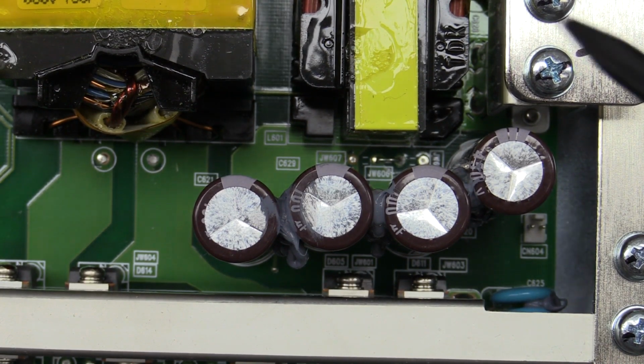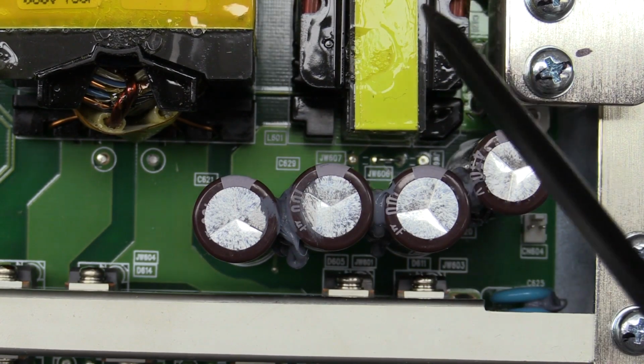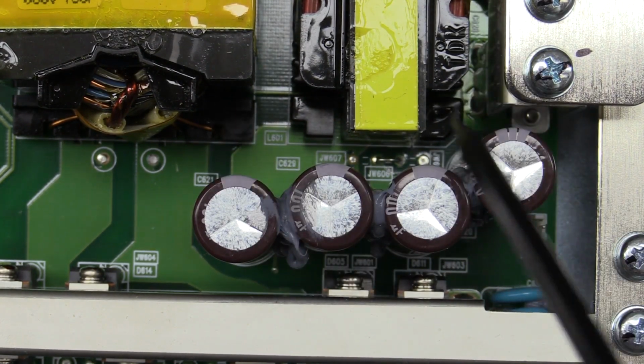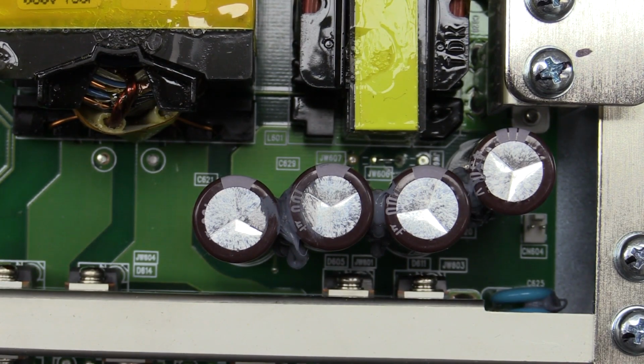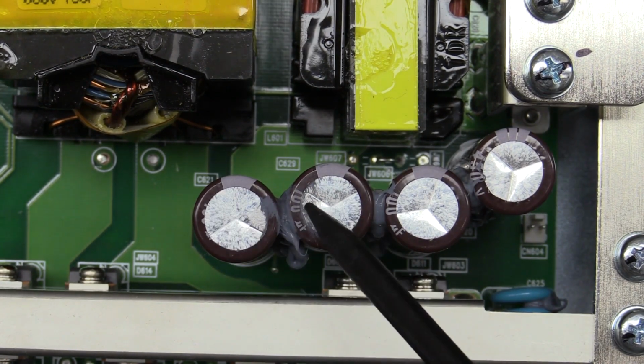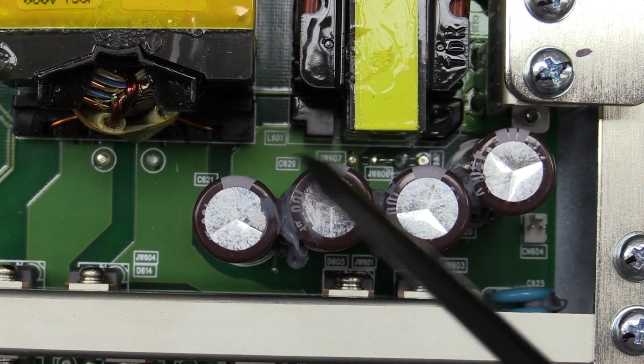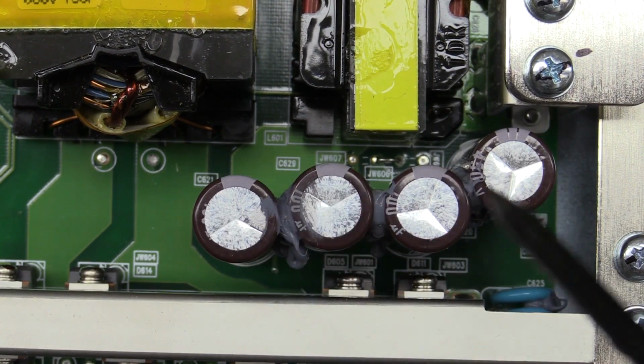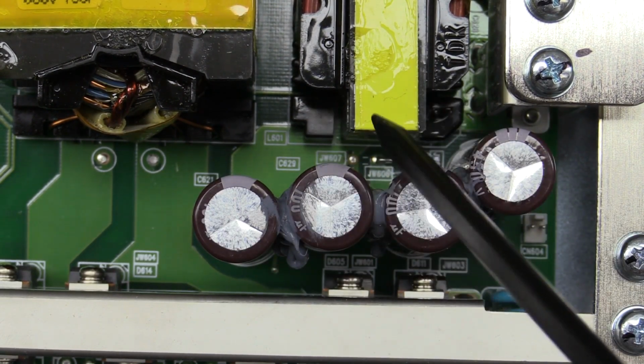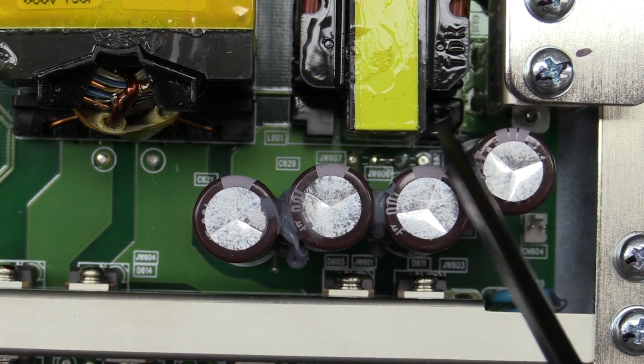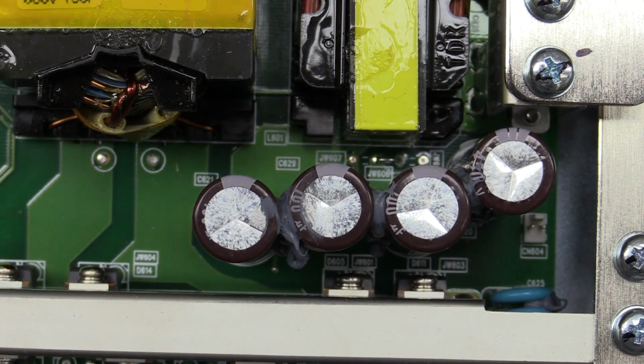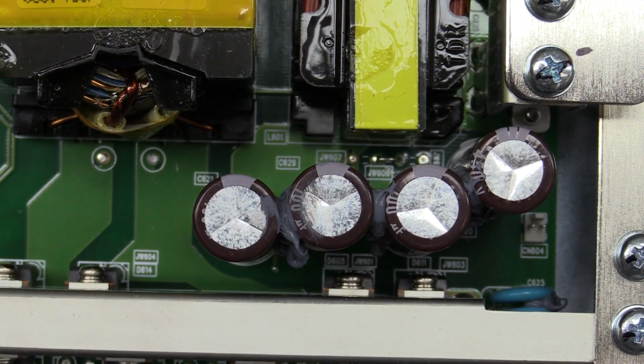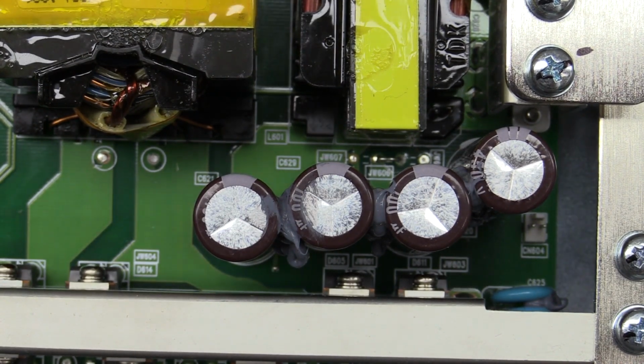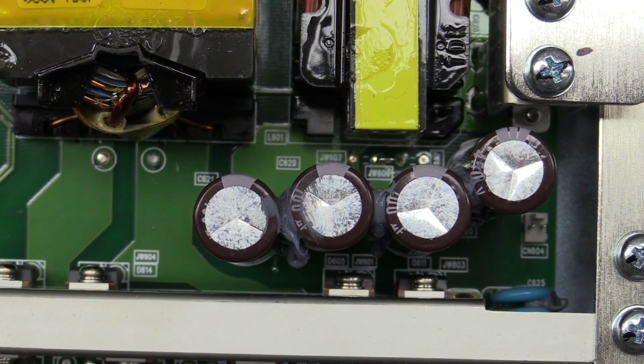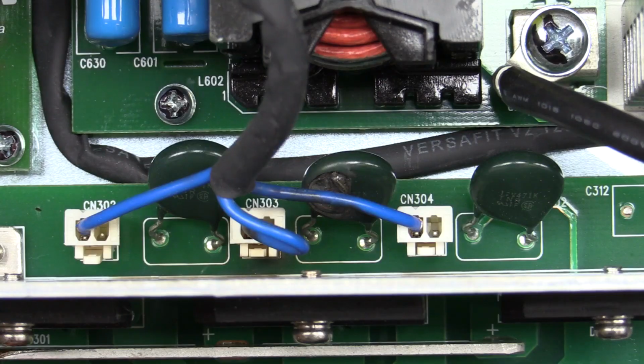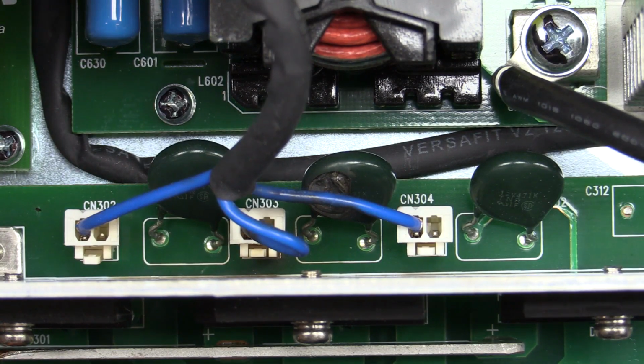So the lower voltage model, they might wire all of these, and for higher current, all 4 of these capacitors in parallel, whereas the higher voltage one like this, the 600 volt one, I believe they are 2 in parallel, and then that group in series with that group to get your higher voltage. And they'd probably have a ballast resistor on there, I'd be guessing, just to equalize the voltage across the two of those. Well, looky what we have here.